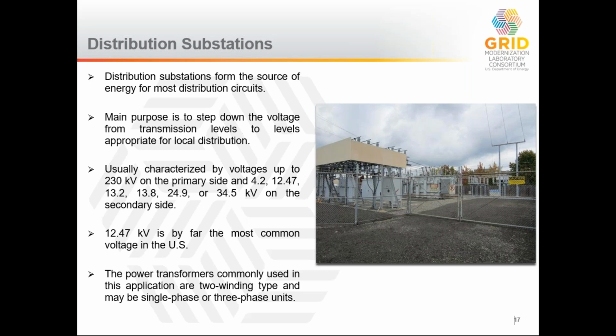The most common voltage in North America is 12.47 kV, but there are a number of other voltages used: 13.2, 13.8, 24.9, 34.5. The trade-off is that the higher the voltage, it allows you to move power more efficiently over distance. However, it requires larger, more expensive equipment. And so this is really the big trade-off that you see in picking these voltages. Now, the challenge is that once you pick the voltage, all of the distribution system equipment uses that. And so if you decide to change the voltage over time, that requires changing out all of the equipment. That can be a very expensive and time-consuming process.